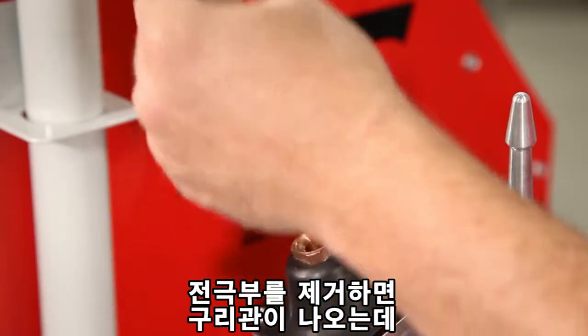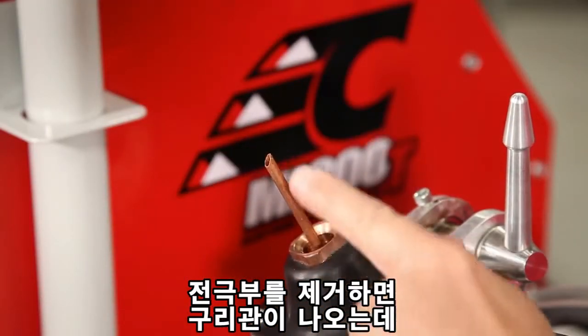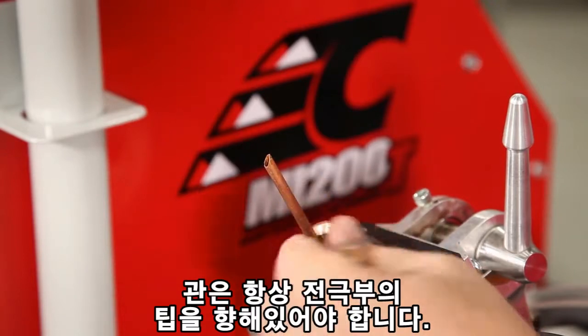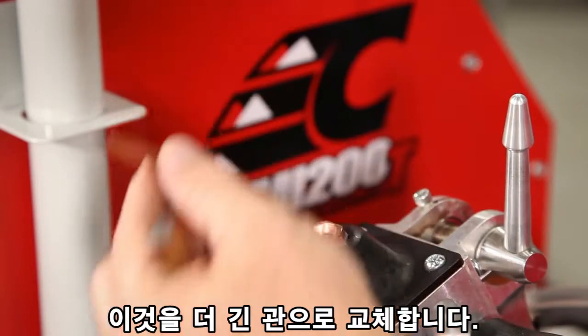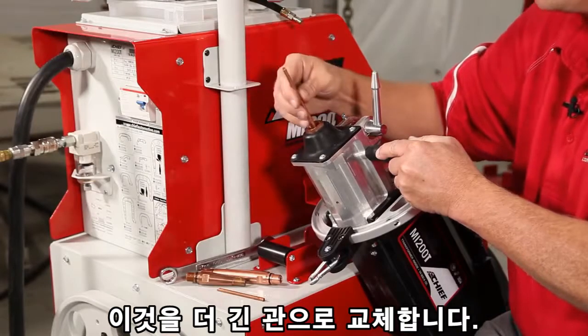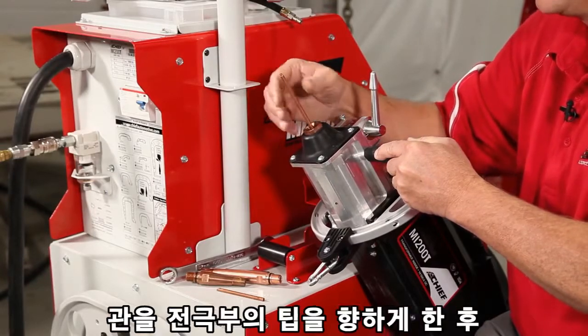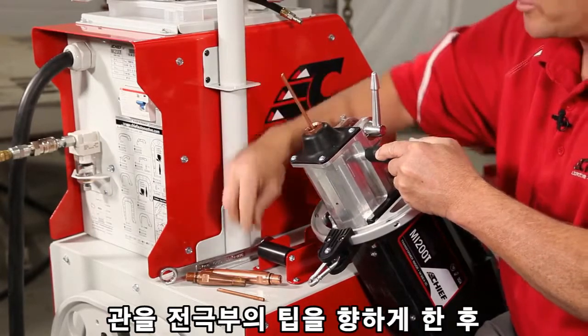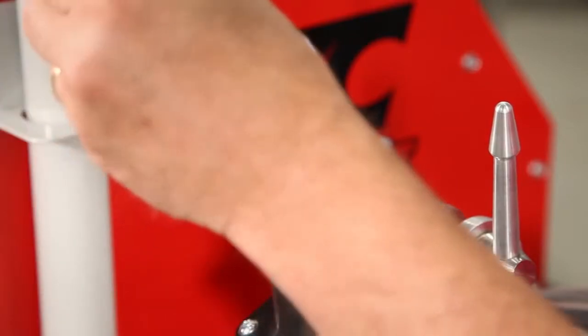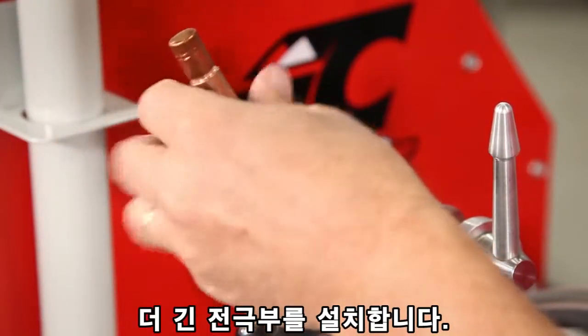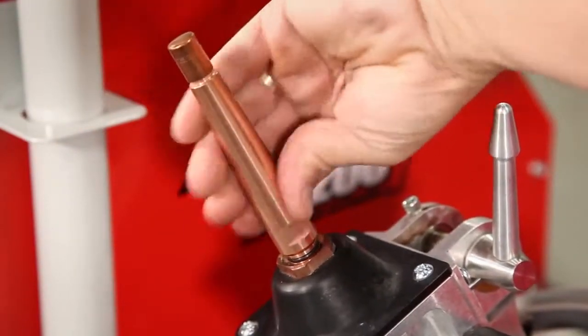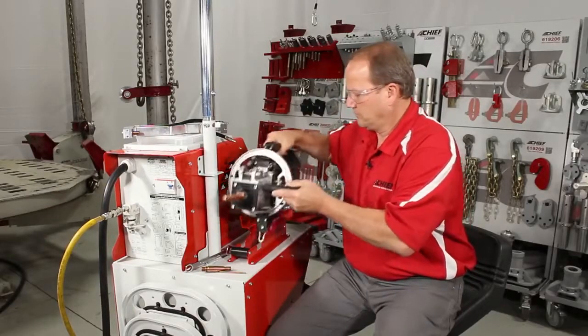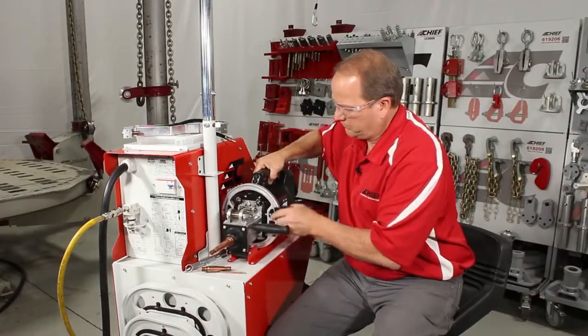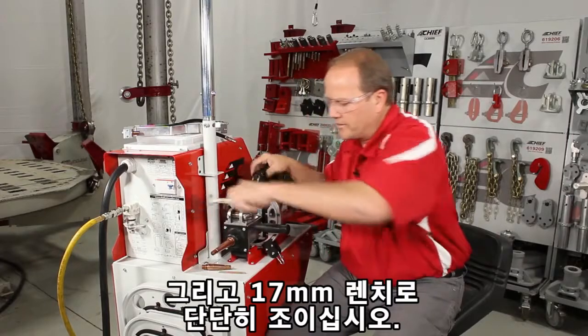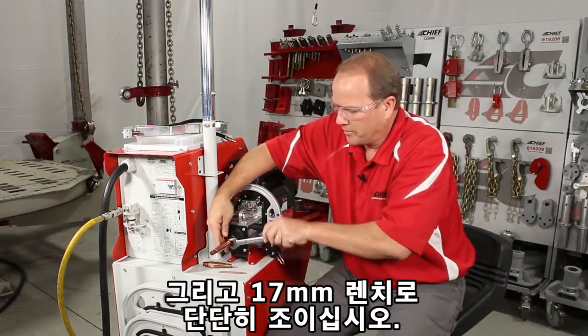You remove the electrode, there's a copper fitting. The taper end is always facing towards the tip on the electrode. Remove that, replace it with the longer tip, and again the tapered end is facing towards the electrode tip, and then reinstall the longer electrode and then secure tightly with the 17mm wrench.